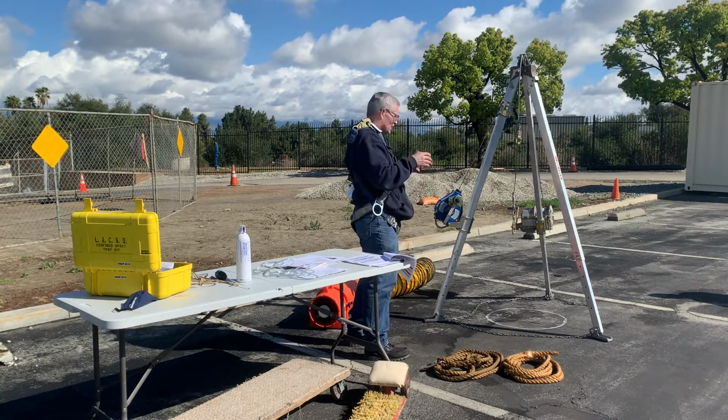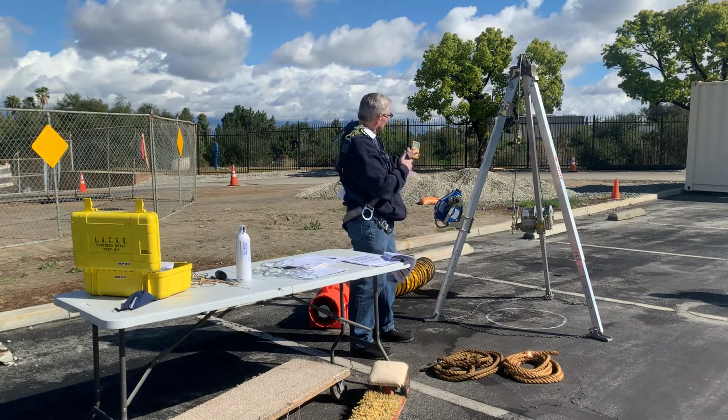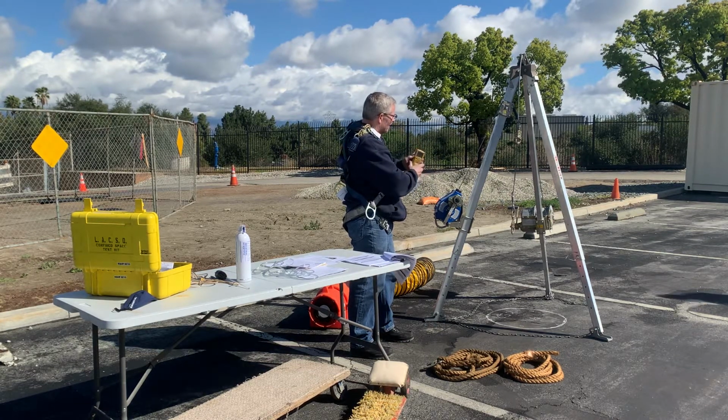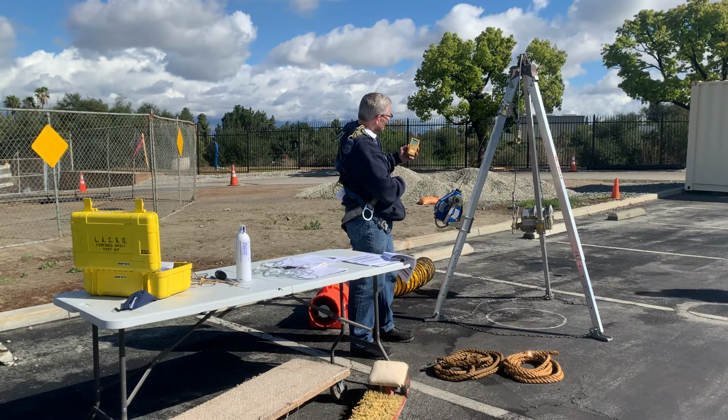So now that this whole thing has been calibrated, even with the bump gas, I have an operating one. So let's say I had to go to another manhole and operate this. This is kind of how the setup would go. I'd restart it, get that sound. It'll go through its checks. There's block the inlet, so I'll block the inlet. Unblock the inlet. It says pump okay. Now it's going through its high setting checks. It's auto zeroing, if you will.